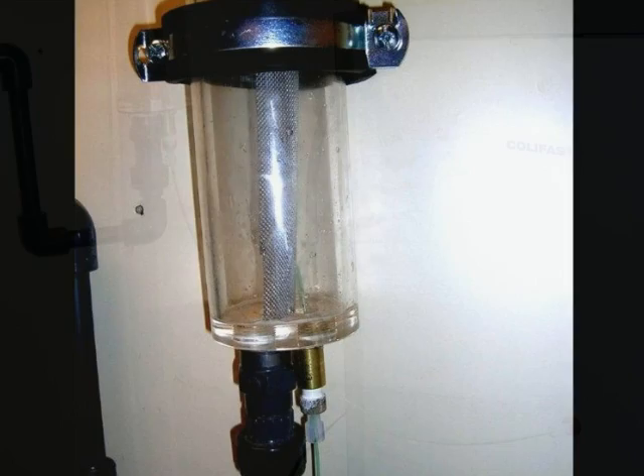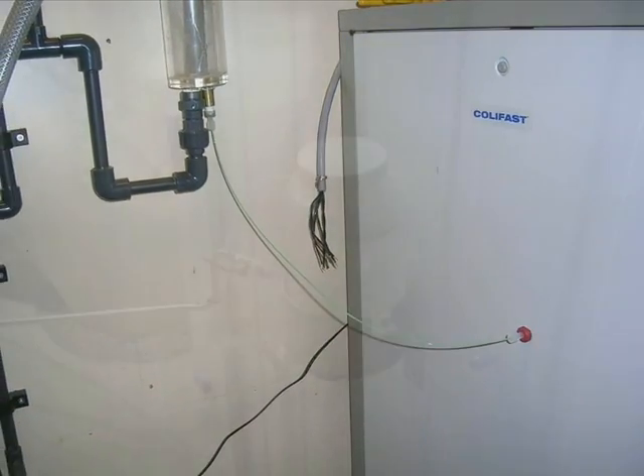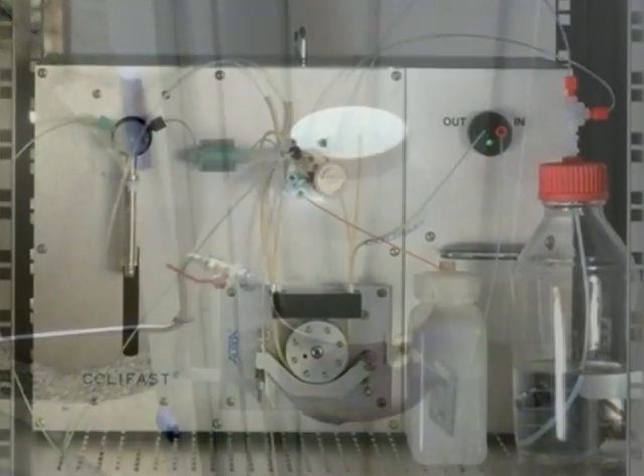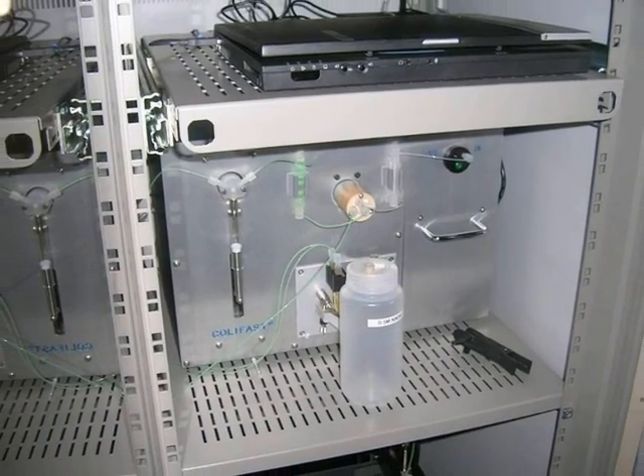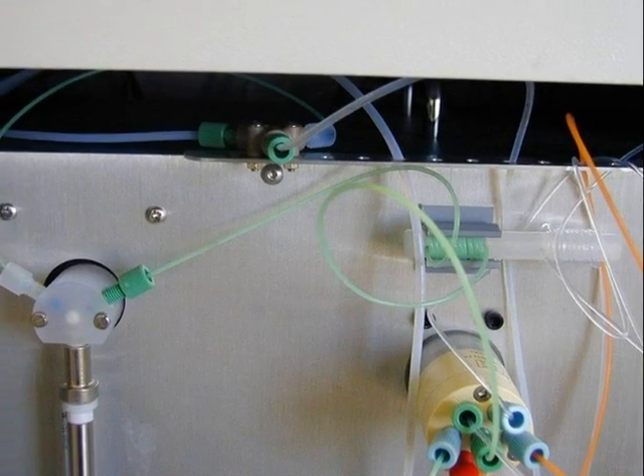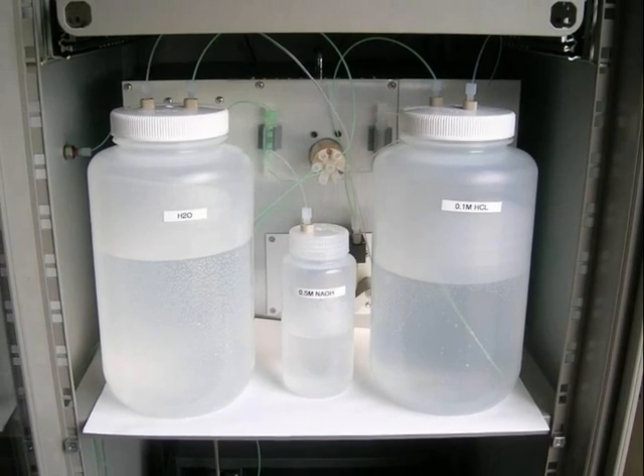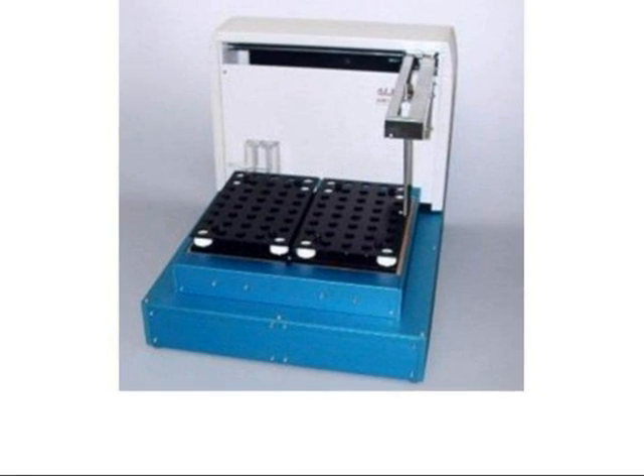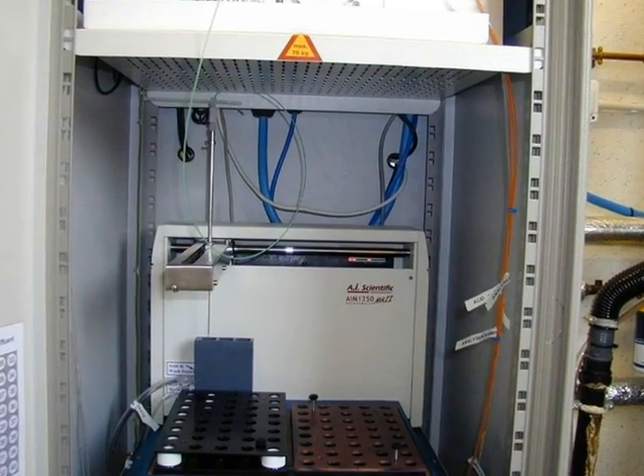From a sampling station, the CALM analyzer will automatically sample flowing water at any location on a schedule predetermined by the operator. Up to 76 water samples are distributed, via the robotic arm of the autosampler, into COLIFAST growth media.